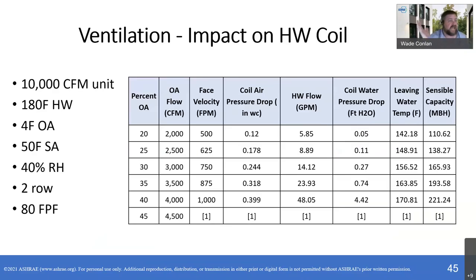I'm going to touch on a couple things that have been added since the guidance came out, and actually is coming back around, which is the impact on a hot water coil. This is in a preheat position, prior to the unit, 100% outside air. We did this with a chilled water coil to see how much more capacity you could get out. On the chilled water coil, we locked in the coil the manufacturer selected and just started increasing the airflow. And you can see at about 45%, 4,500 CFM instead of 2,000, the manufacturer's coil selection program said, do not run this coil here. So if you're going to increase ventilation, which Lindsay showed is potentially a higher cost than filters and other things, sometimes the limitation is actually on the coil, and sometimes it's on the plant or the heat source itself.